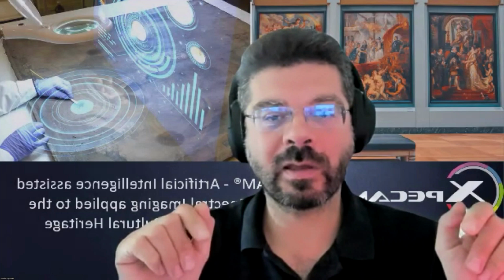Now, in terms of the spherical aberrations of the objective lens that we're using, we are performing correction if we know which objective lens we're using. So for the ones that we provide with the system, we have a correction of the spherical aberrations of the objective lens that is applied later on the platform, and that's why you don't have any, let's say, misalignment of the points across the different parts of the images that are used for stitching. So intensity is corrected, spatially it is corrected, and that's why the result seems so fantastic for the stitching.